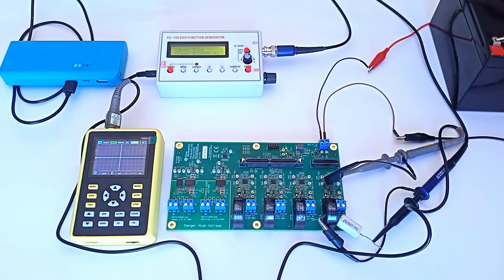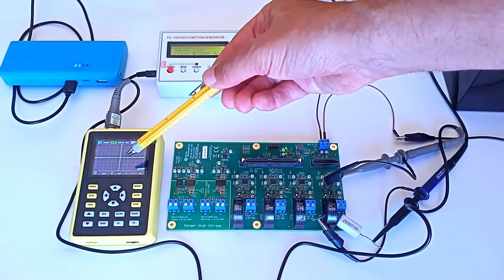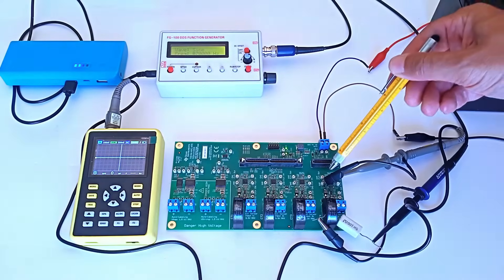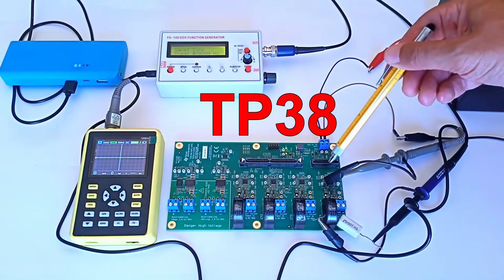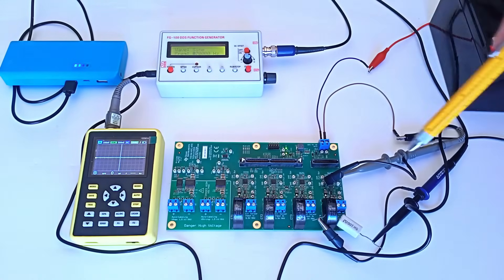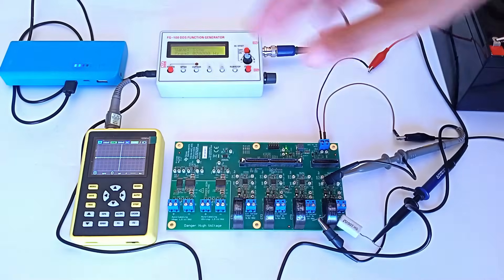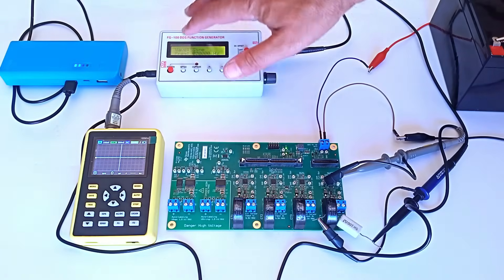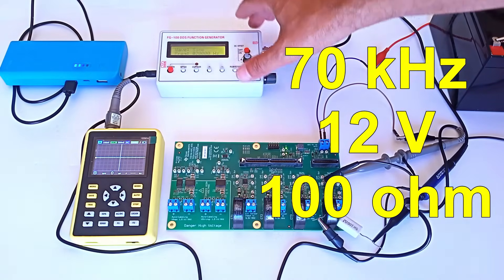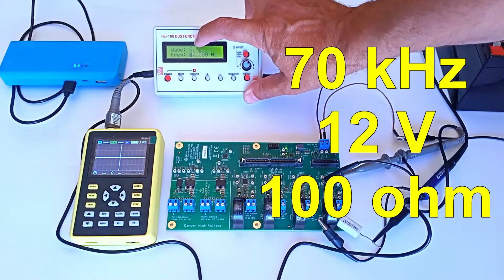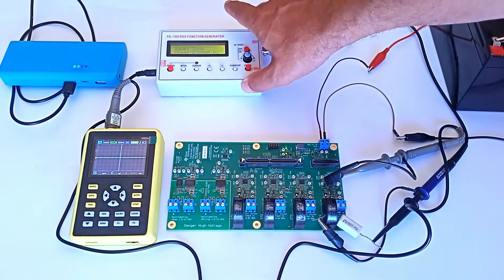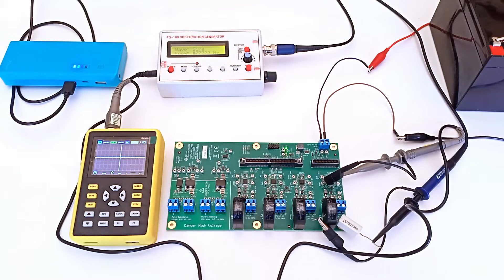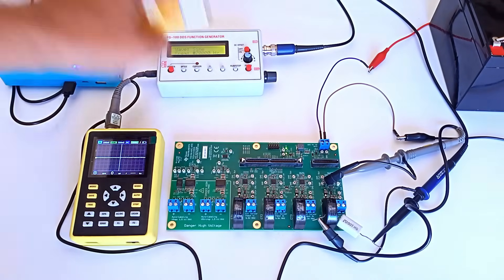An oscilloscope measures the amplified and filtered signal on TP38 and GND. The arc signal is generated at a frequency of 70 kHz at 12 volts on a 100 ohm load. Without the arc, the signal is flat.